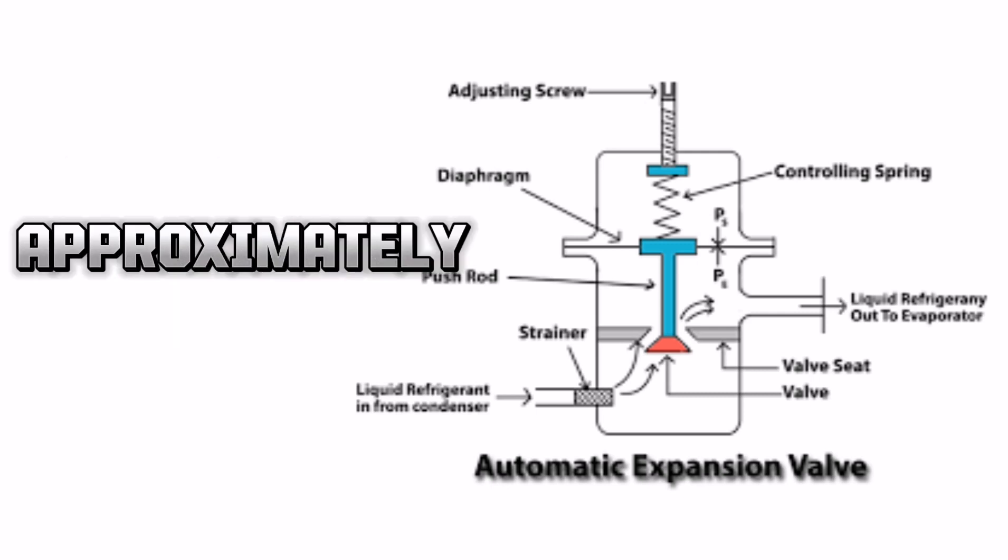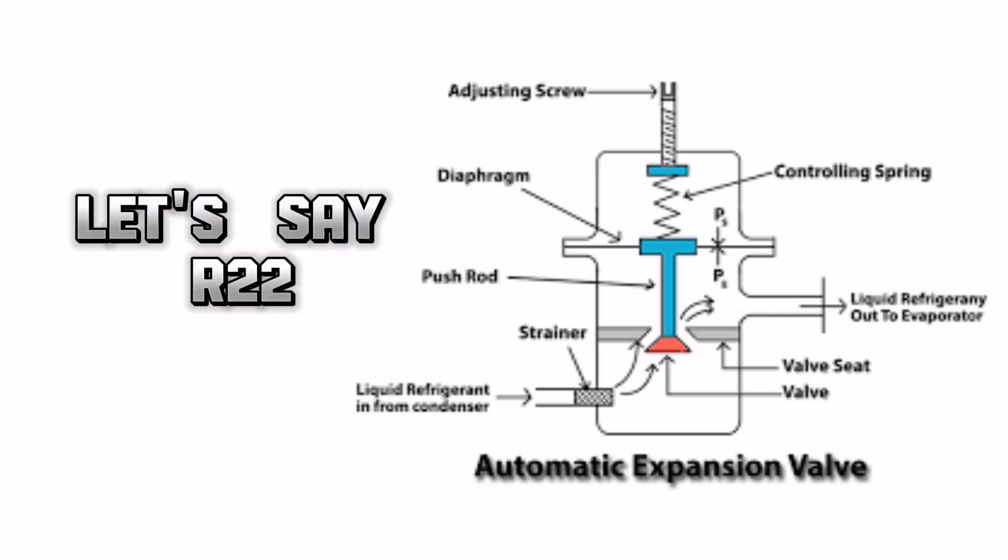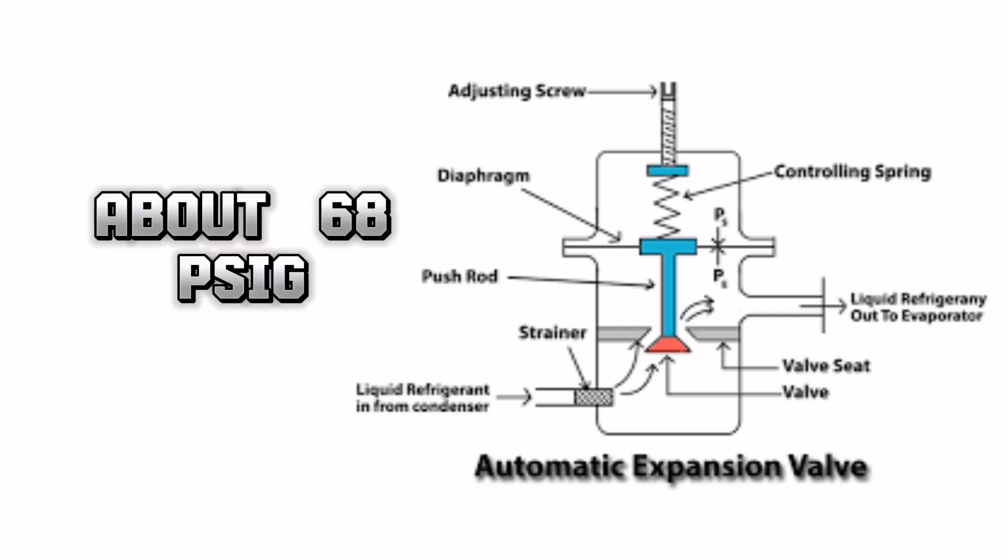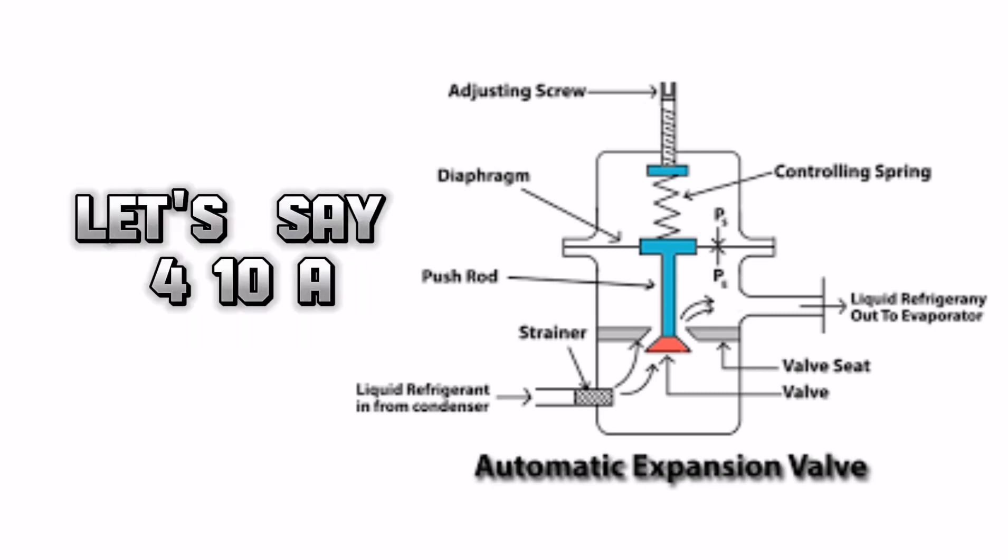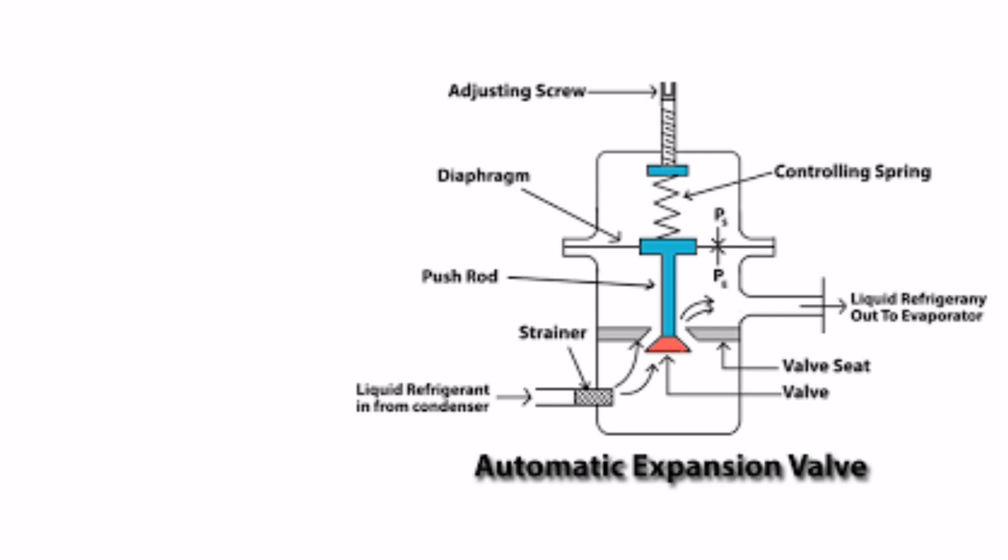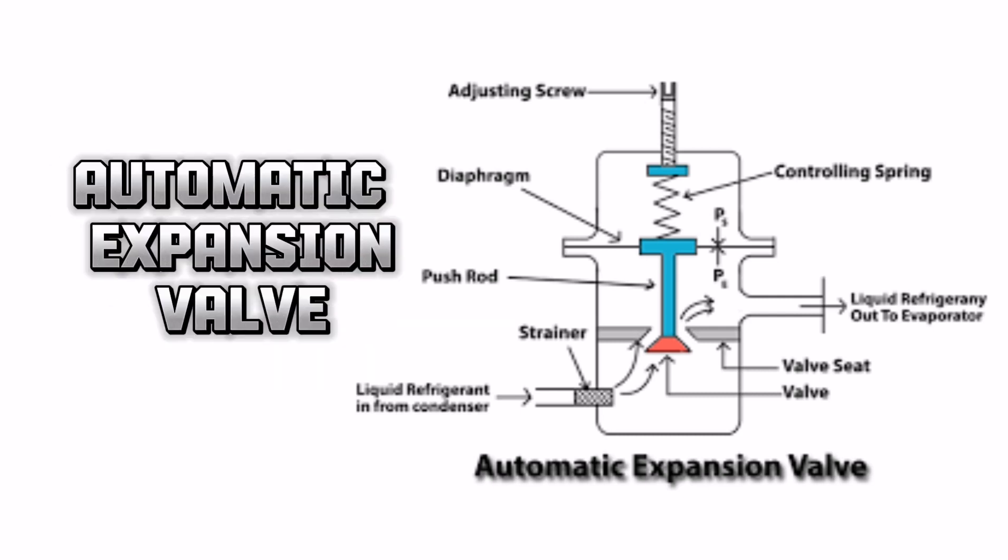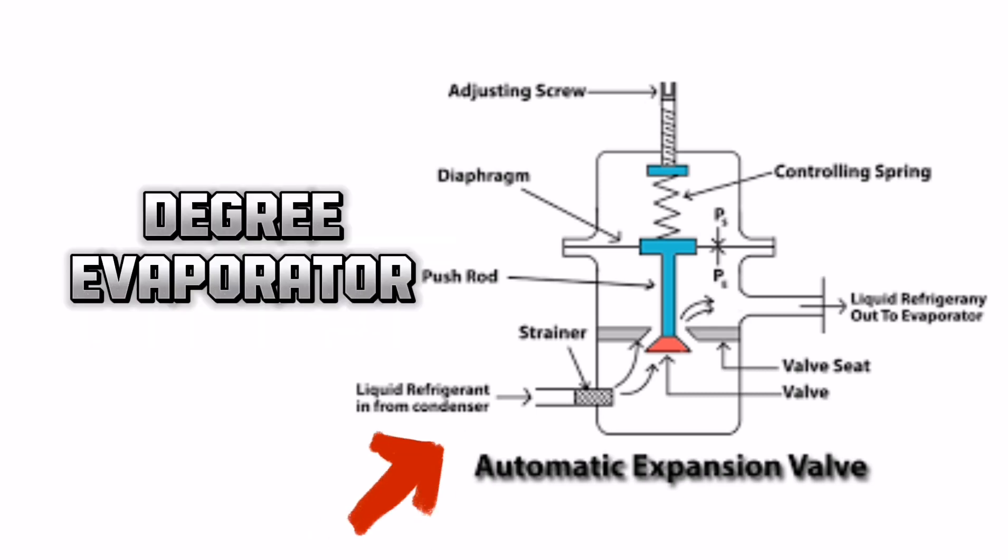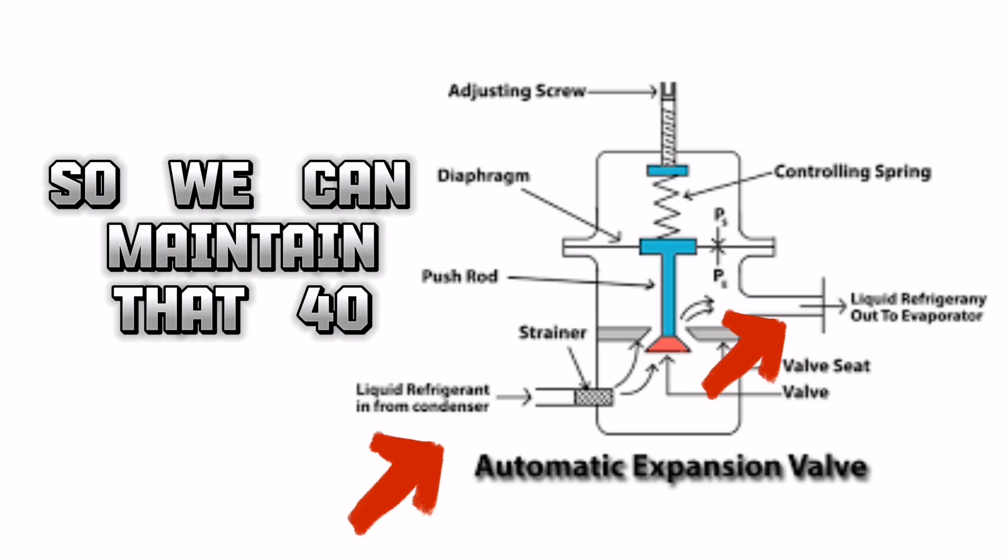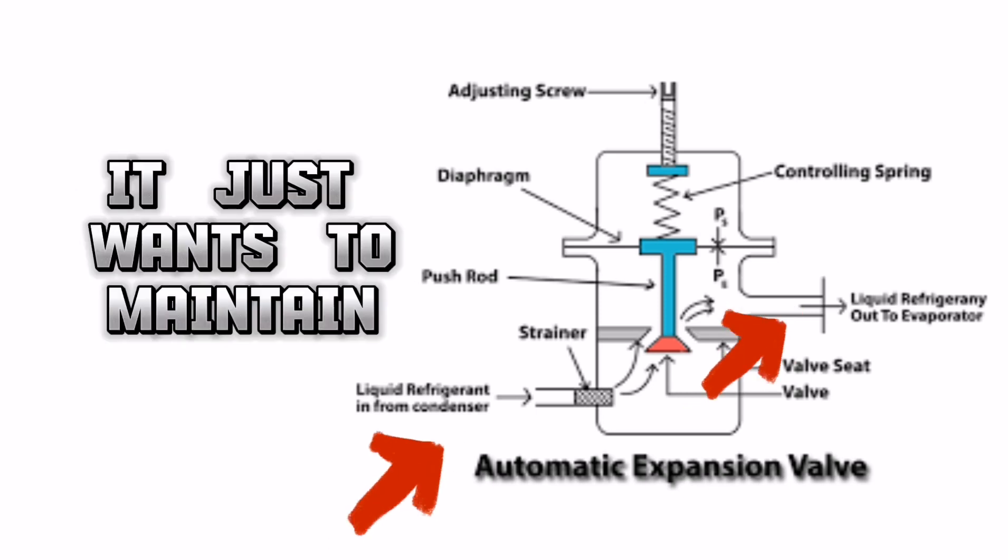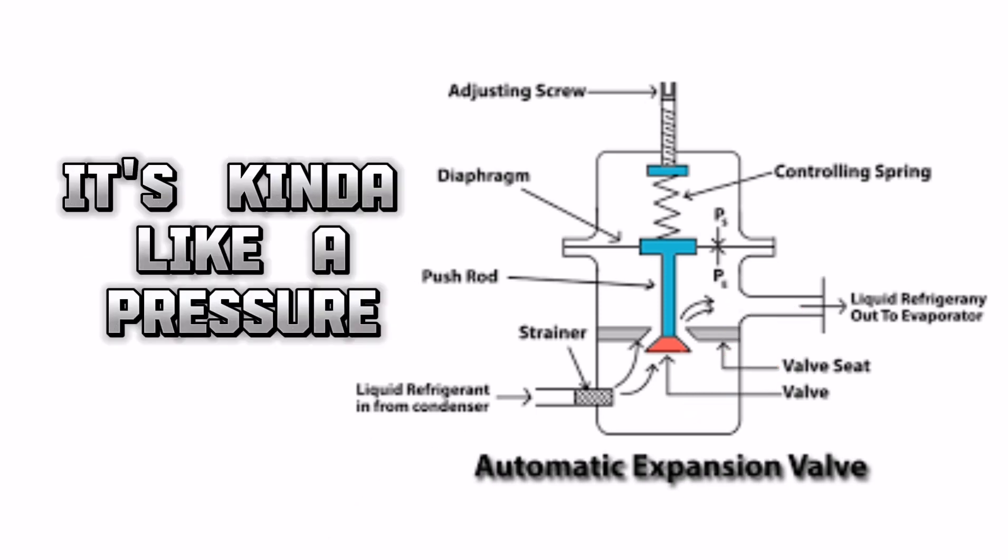But if we're looking at an R22 system, we're going to need approximately, let's say, 68 PSIG. If we were dealing with, let's say, 410A, then we're looking at about 118 PSIG. Somewhere around there. And that's going to give us 40 degrees. The automatic expansion valve is going to maintain the pressure, this pressure here, so that we can get a 40 degree evaporator. So we can maintain that 40 degree evaporator. It's not going to care about superheat. It's not going to care about subcooling. It just wants to maintain that pressure. It's kind of like a pressure regulating valve.